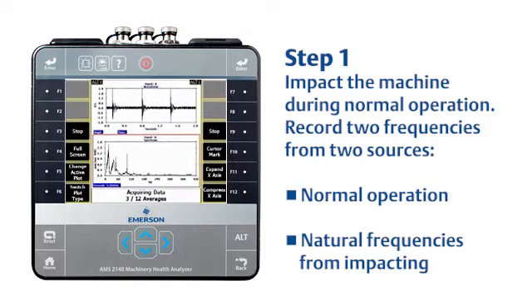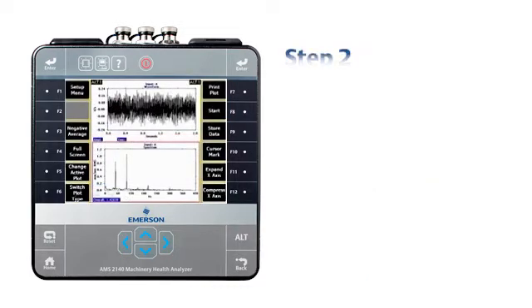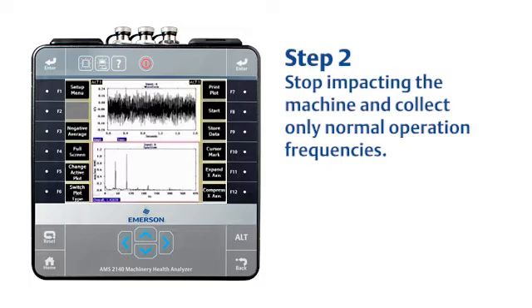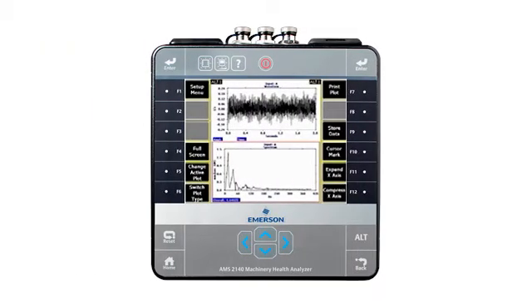The AMS 2140 will have you do 12 averages before guiding you to the next step. In step two, you will not continue striking the machine. Without the impacting, the peaks you see now are associated only with normal operation frequencies. The analyzer will compare and subtract the results of the two images from each other, creating a third image. In this spectrum, only the natural frequencies are still shown.